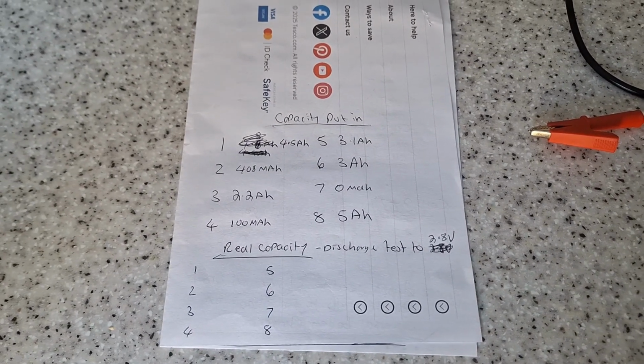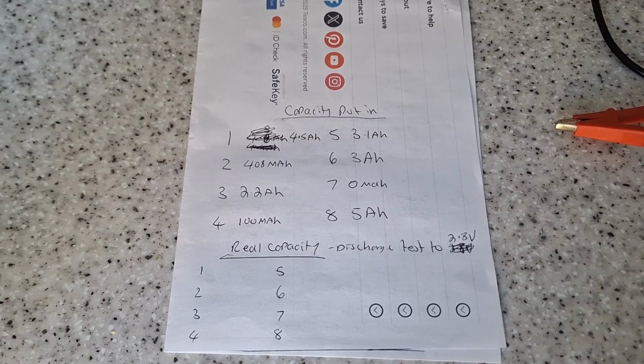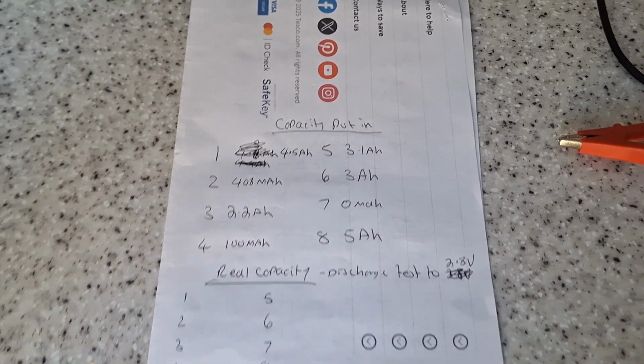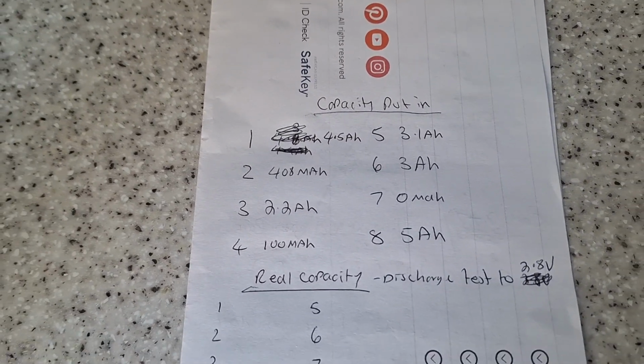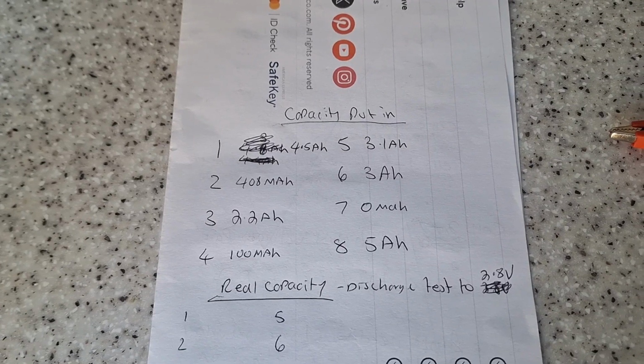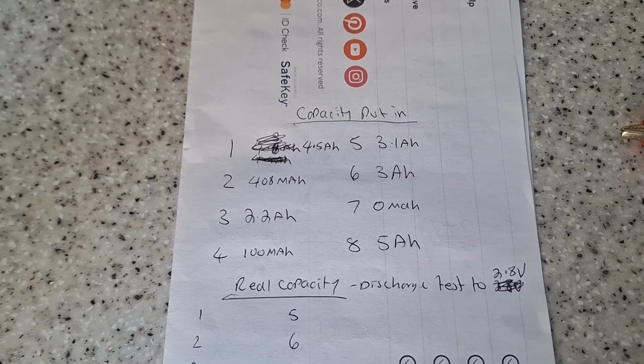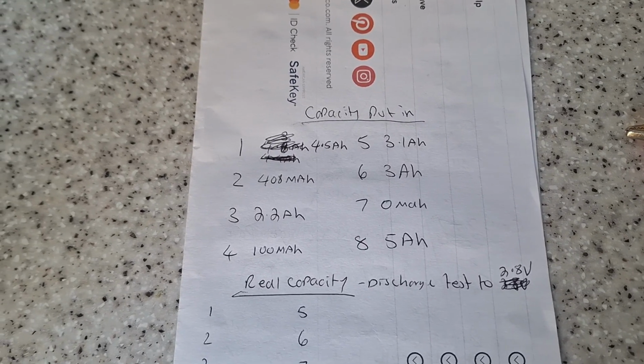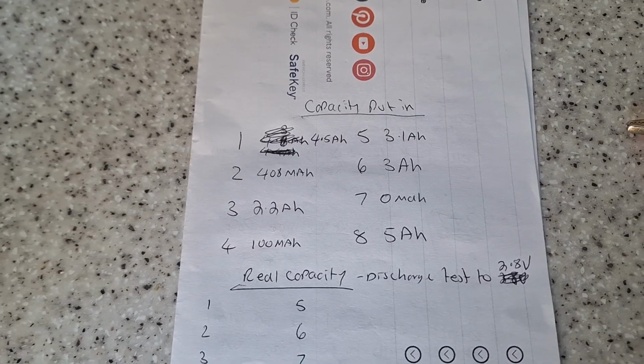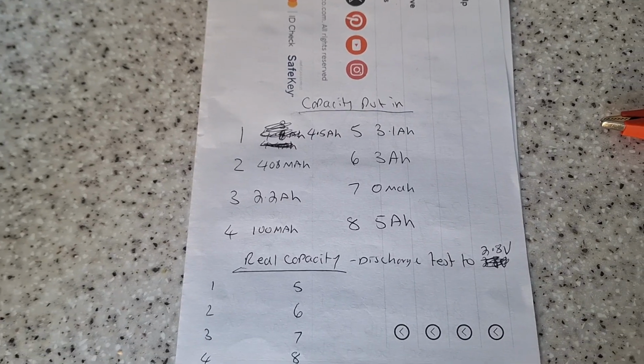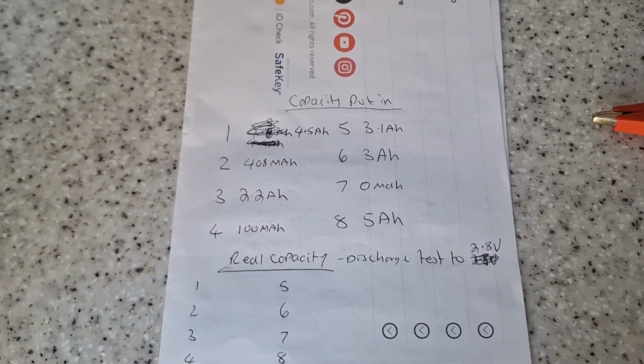It's a very time consuming process, so this is going to have to be done over a period of a few weeks. It just goes to show you can't simply tell a battery's capacity by the voltage alone. You must do a discharge test, recharge it, and then test it again. That's the only way you can tell what the true capacity is.